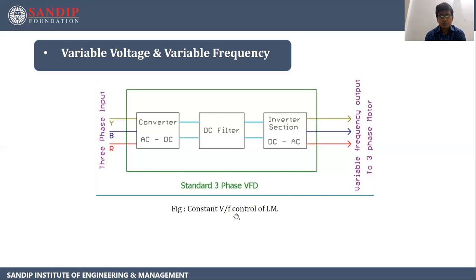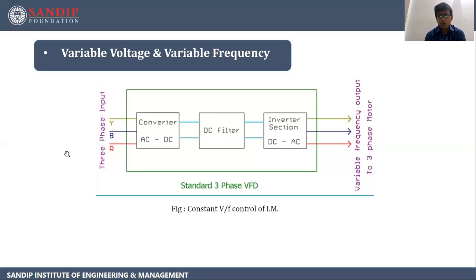To achieve V by F constant, we have to vary both V and F. Let's see this block diagram. It consists of a converter that converts AC into DC. The input is three-phase constant voltage, constant frequency supply, which is fed to the AC to DC converter and gets converted into DC. This DC is passed to a DC filter so ripples are removed, and later it is passed to the inverter section. The inverter section converts this DC into AC of variable frequency and variable voltage. As the output is variable frequency and variable voltage, the V by F ratio remains constant. Therefore this is called variable voltage, variable frequency (V/F) control of induction motor.